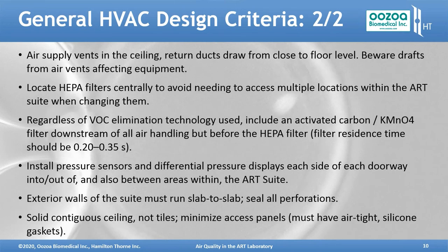In terms of the air supply vents, they go in the ceiling, and the return air ducts draw from close to floor level, usually towards the corners of the rooms or in the middle of the wall as well, if it's a big space. Beware of drafts from air vents affecting equipment. So if the air vent is in the ceiling, don't locate it above benchtop incubators. You need to ideally locate the HEPA filter centrally to avoid needing to access multiple locations within the ART suite when changing them.